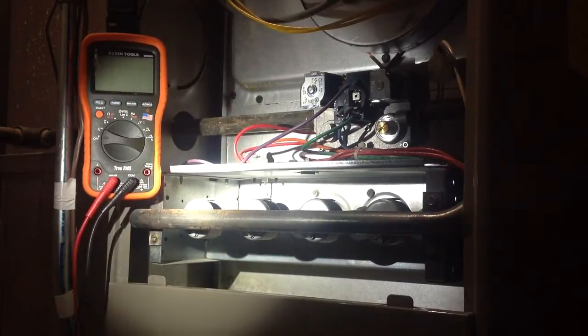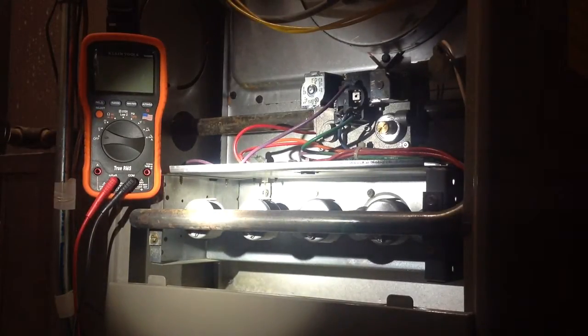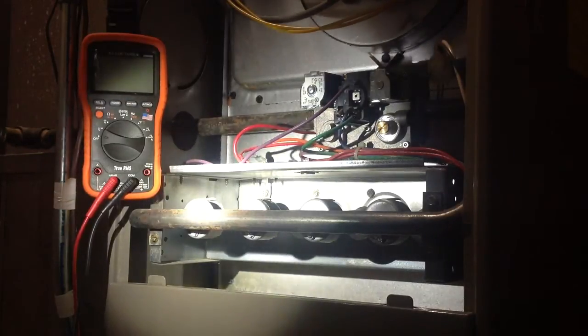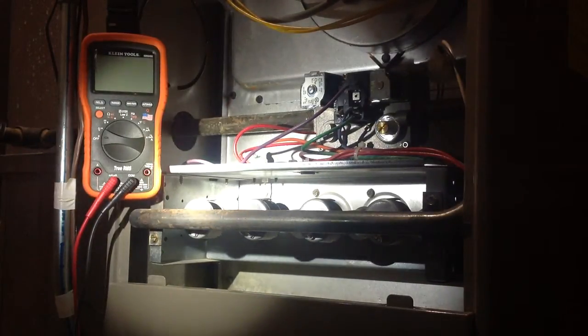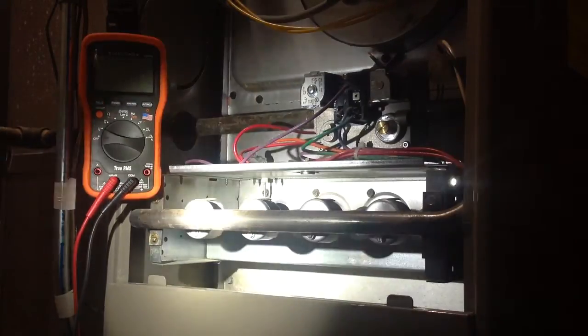Now, flame is not very conductive. It's not like copper wire, so it has a lot of resistance, and it takes a lot for that voltage to get through the flame. So you only have microamps of current flowing through. Even though it's an AC signal that's applied, the flame kind of rectifies it, and it ends up being a DC signal. So when we measure microamps, you primarily want to look at microamps as a DC function.